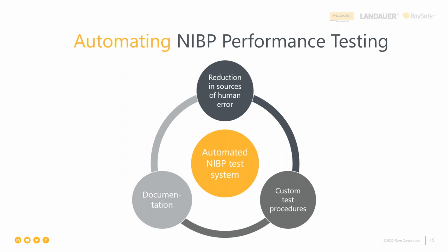We call this workflow automation software, and interoperability means the software tells the test instrument how to configure itself for the test we want to do and automatically collects the measured values. The predetermined pass or fail criteria are built into the workflow, so it's automatically in there. But you're still going to interact with the medical device to set up the measurement that needs to be made. So you're going to push the button to start the NIBP, for example. So you're not hands-free here, but you are eliminating sources of human error.